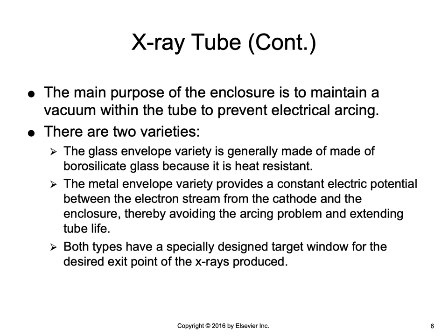The main purpose of the enclosure is to maintain a vacuum within the tube. Because x-ray production involves the interaction between the filament electrons and the anode target, if any air was present, the electrons from the air would contribute to the electron stream, causing arcing and damage to the tube. The glass envelope variety is generally made of borosilicate glass because it is heat resistant. However, as these tubes age, vaporized tungsten from the filament deposits on the inside of the glass, causing a sun-tanning effect due to bronze discoloration, which causes problems with arcing and damage. The metal envelope variety provides a constant electric potential between the electron stream from the cathode and the enclosure, thereby avoiding the arcing problem and extending the tube life.